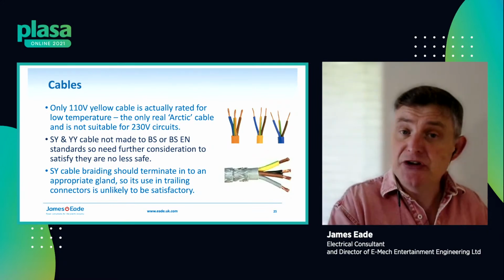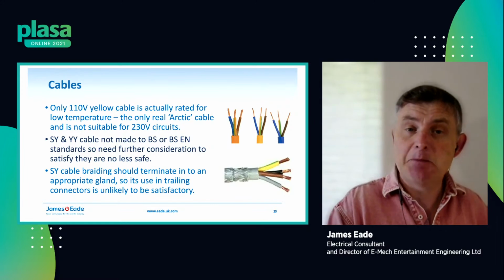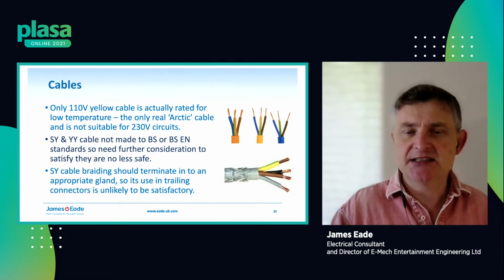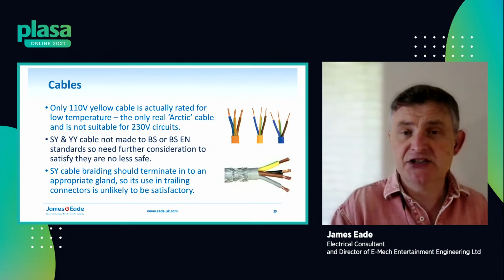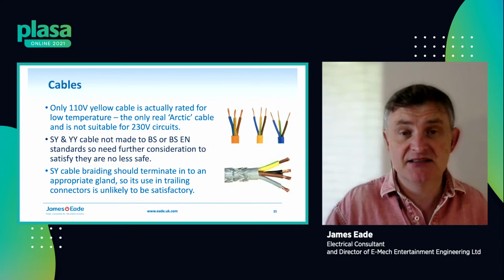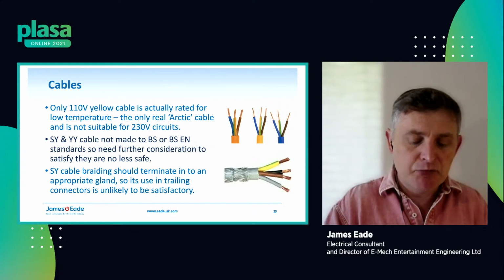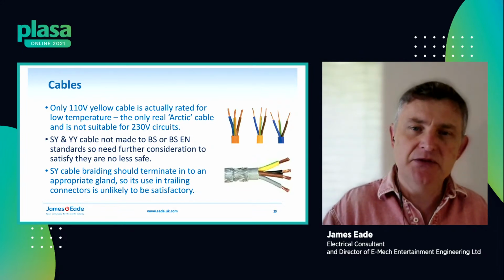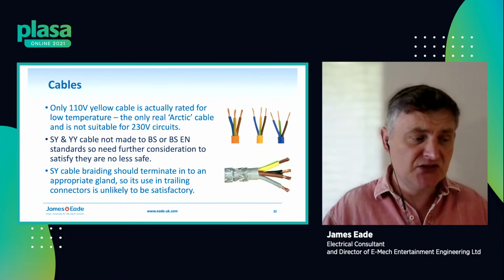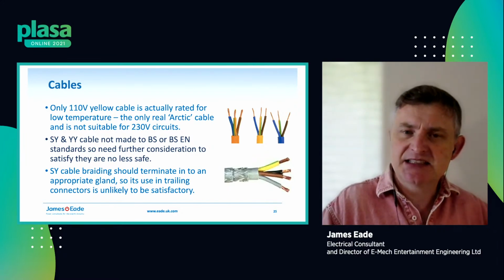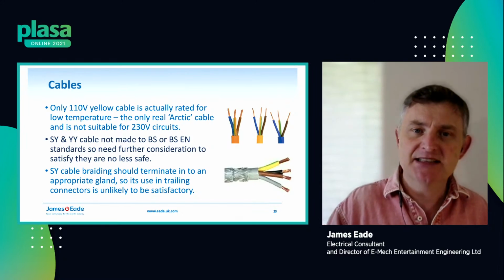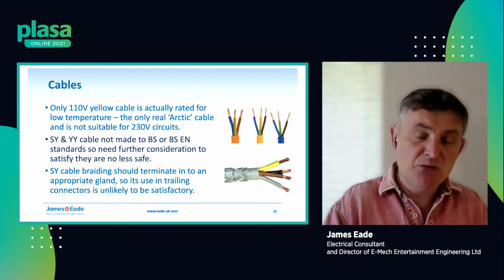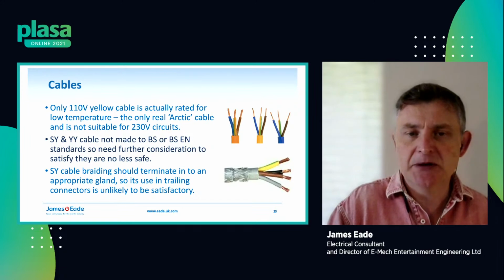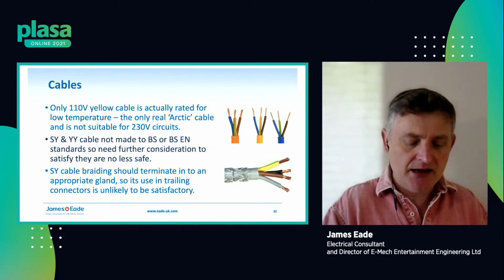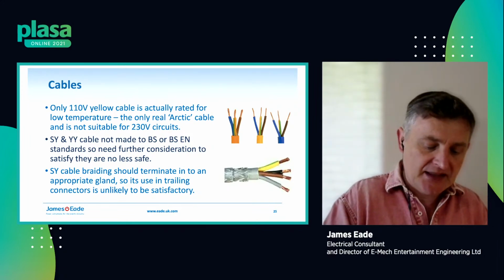It means that if you're using it in an installation in the UK, as the designer, you've got to state under the wiring regulations why you think it's suitable for that use and how it meets the requirements for safety. The braiding on that cable is really there for interference suppression, and it's commonly used on machine tools and other equipment that has to move periodically for maintenance. But it's almost like flexible metal conduit is the way to think of it. So it provides that interference suppression.